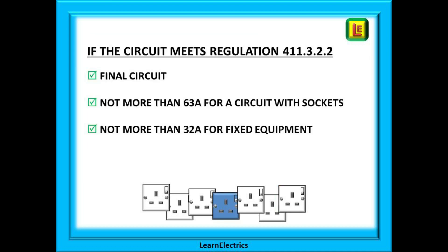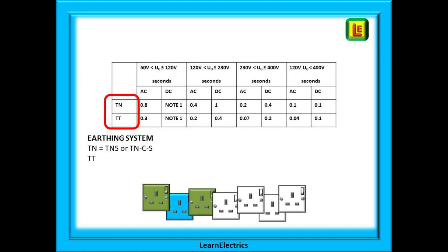Moving on: if the circuit meets regulation 411.3.2.2 then it will be a final circuit and will not exceed 63 amps for a circuit with sockets, nor exceed 32 amps for a circuit with fixed equipment. We are going to use table 41.1 now for a few examples.